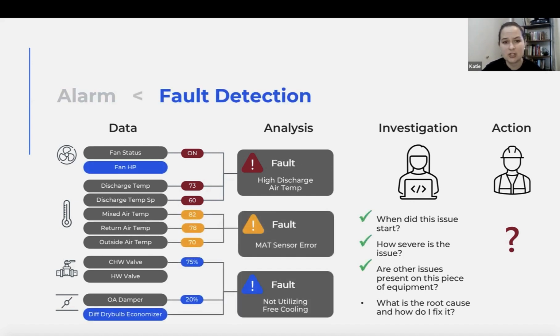If you have fault detection and you get that high discharge air temp fault, you know when it started because you have some history. They bring that to you. You know how severe it is because maybe you know that it serves a lab space. Maybe you have prioritized lab spaces to have a higher maintenance priority.